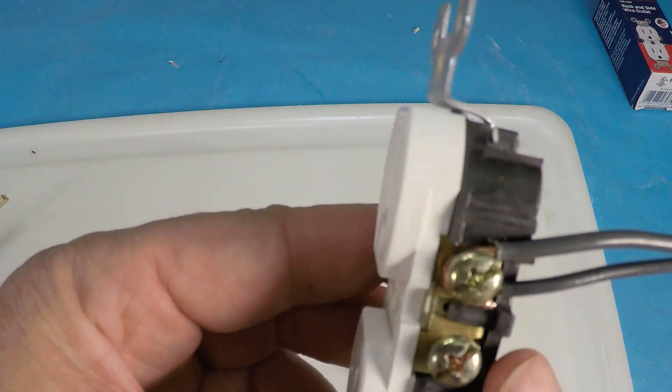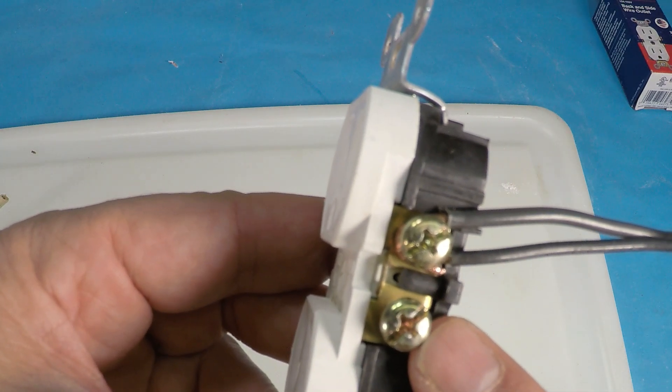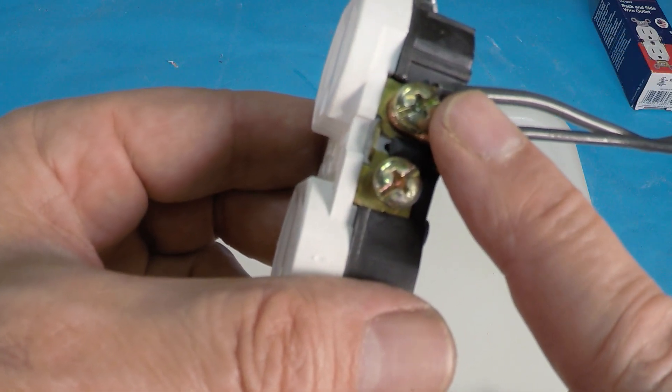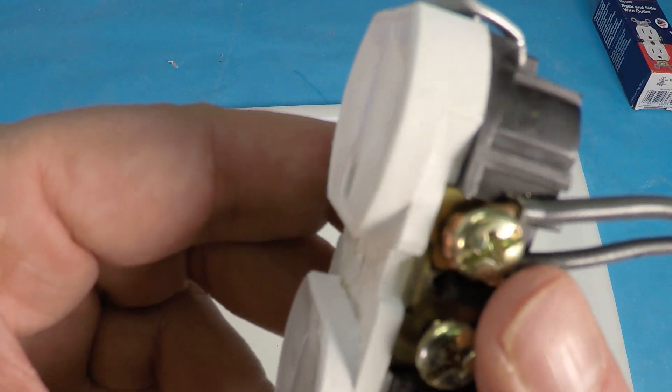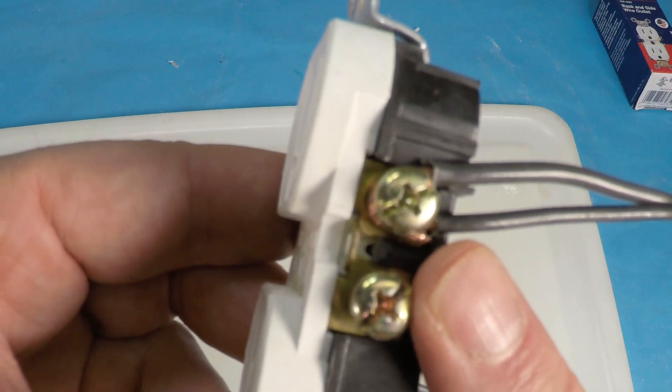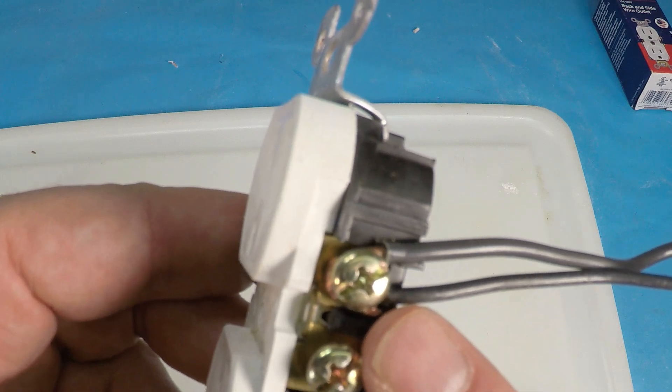Let's go to another one that we see often. People are doubling up. Maybe this one was taken by another load wire and you want to have another wire to go someplace else. Doubling up here is an absolute no-no. You cannot do this. Something's going to slip off here, you're going to have arcing. This is extremely dangerous. Never do it.